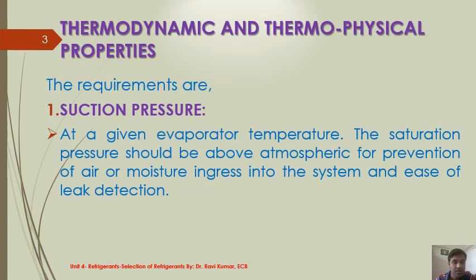This is required because if any leakage takes place from the system to the surroundings, the refrigerant leaks out from the system, which is easier to handle than the reverse case. If the system is operating under vacuum, moisture from outside leaks into the system, which is difficult to handle because complete overhauling of the system is needed to remove air or moisture. Also, detection of leaks is difficult under vacuum. So as far as possible, the refrigerant should have a positive pressure at evaporator temperature.